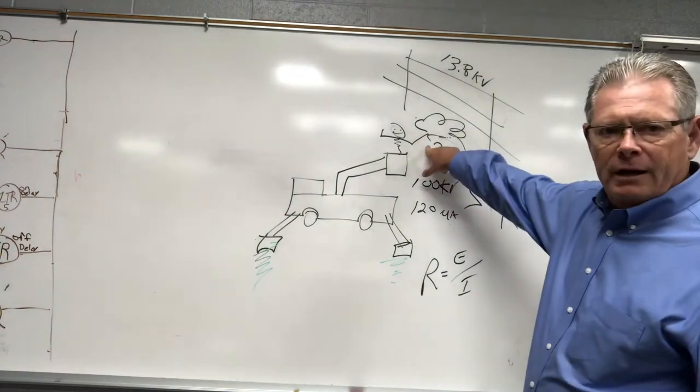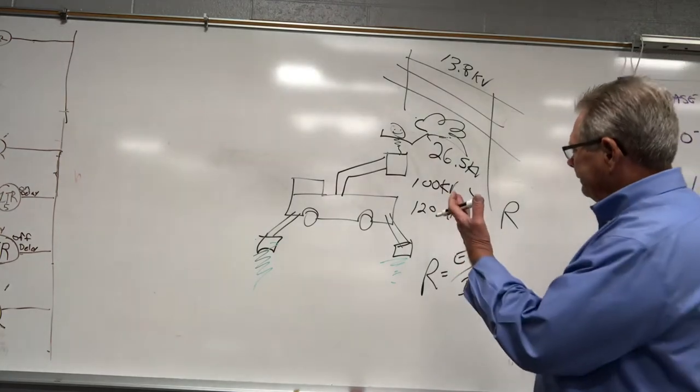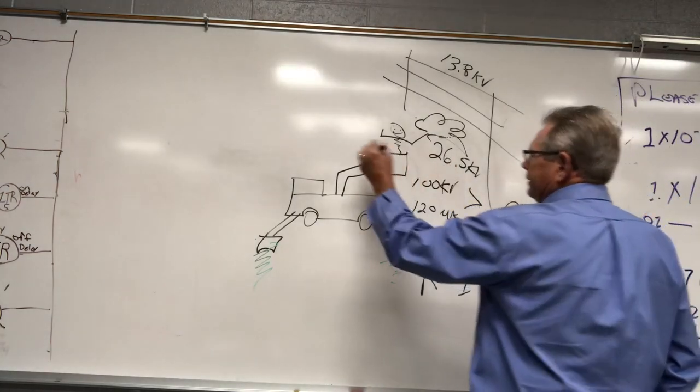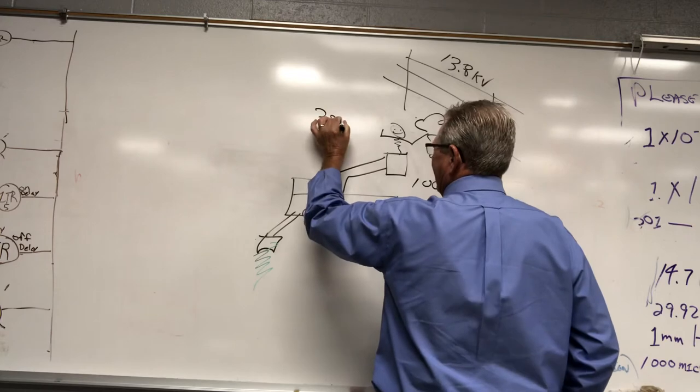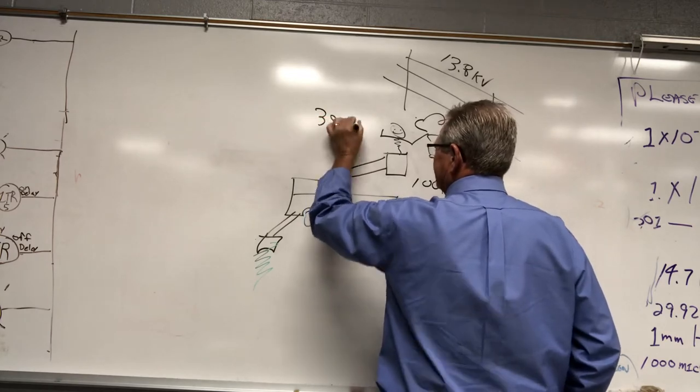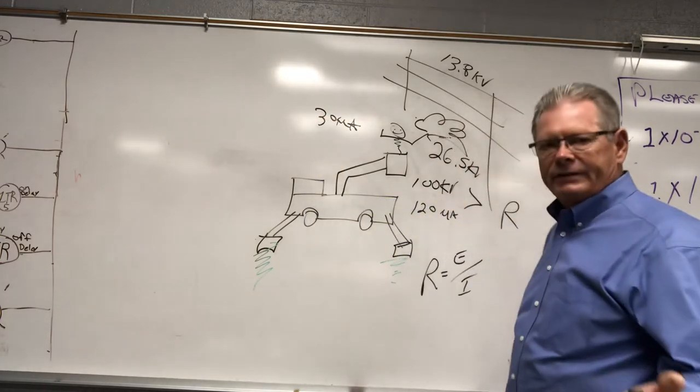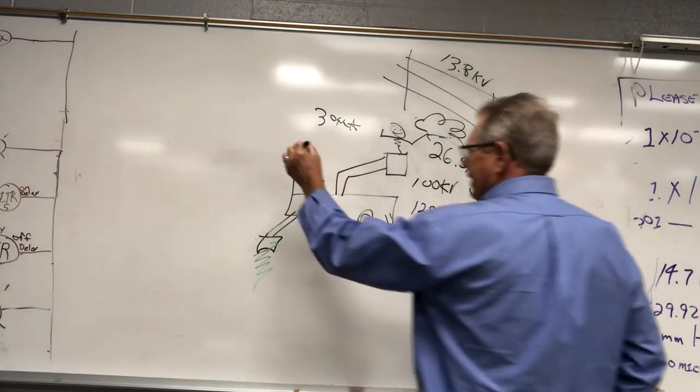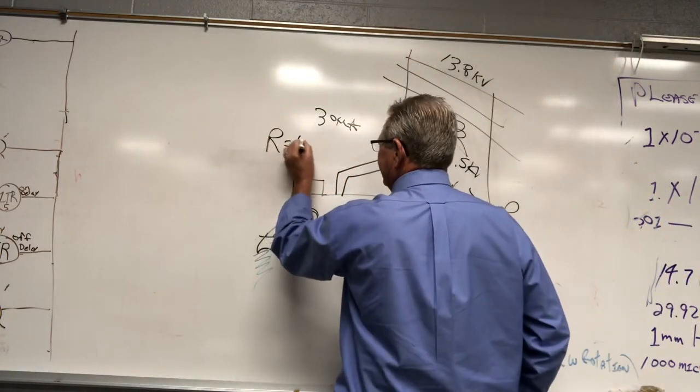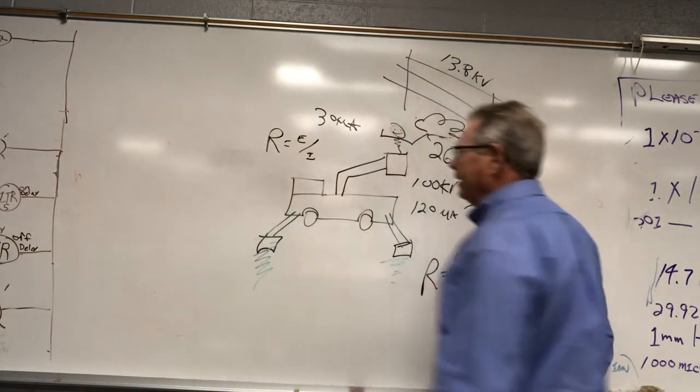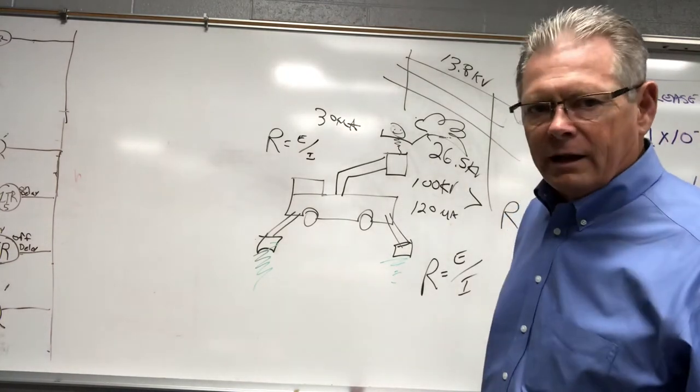Same thing for the glove. If the glove passes 30 microamps at 26,500, same thing. Resistance equals E voltage divided by current, and we get a resistance for the glove.